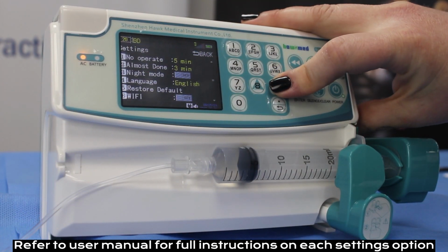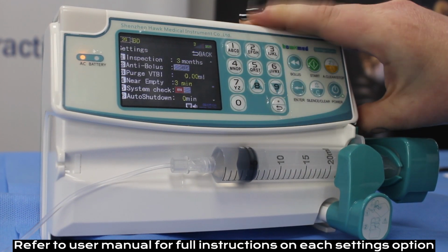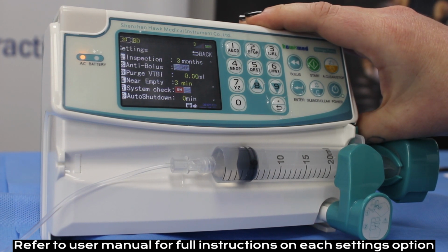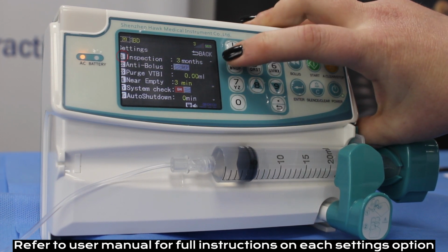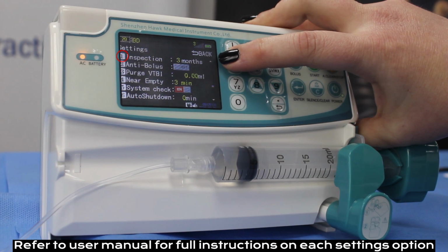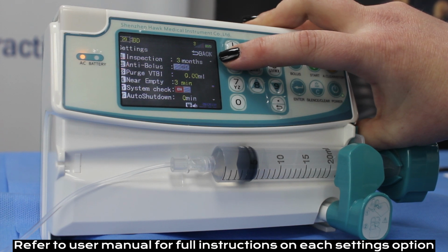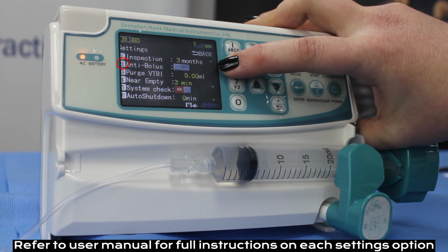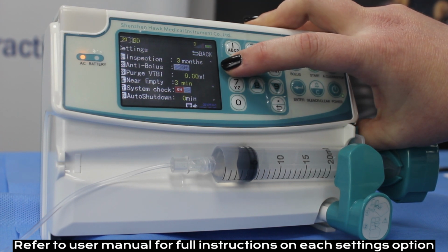Moving down again through our settings menu to the next page, we have a few more options. We can set an inspection alarm. In this case it's set 3 monthly, so an alarm will be triggered when an inspection's due. The anti-bolus feature can be turned on or off, and this can help reduce the risk of a bolus being administered when an occlusion has been cleared.